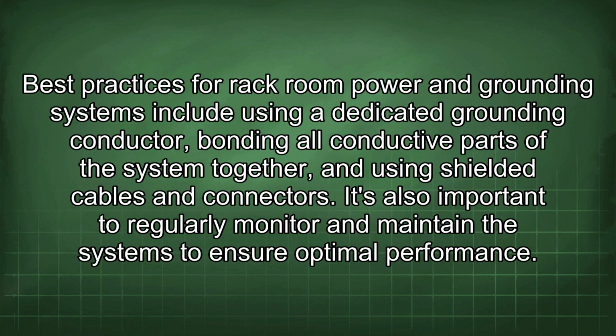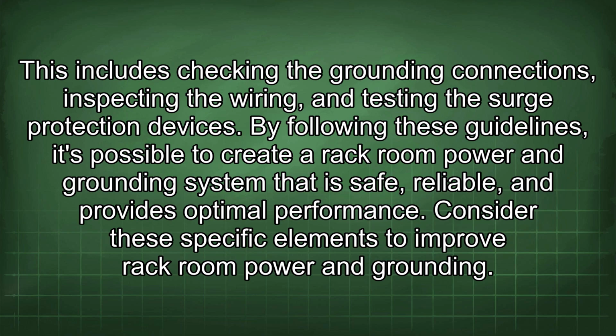Best practices for rack room power and grounding systems include using a dedicated grounding conductor, bonding all conductive parts of the system together, and using shielded cables and connectors. It's also important to regularly monitor and maintain the systems to ensure optimal performance. This includes checking the grounding connections, inspecting the wiring, and testing the surge protection devices. By following these guidelines, it's possible to create a rack room power and grounding system that is safe, reliable, and provides optimal performance.